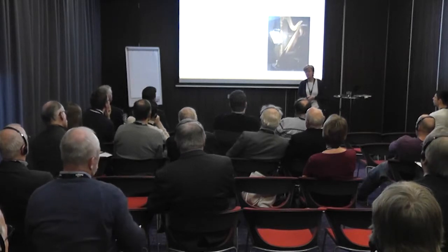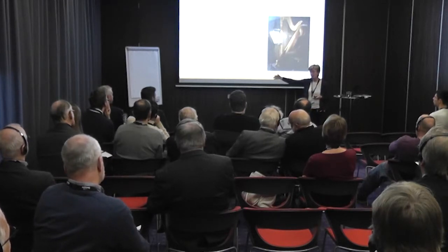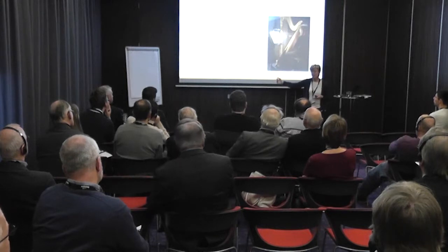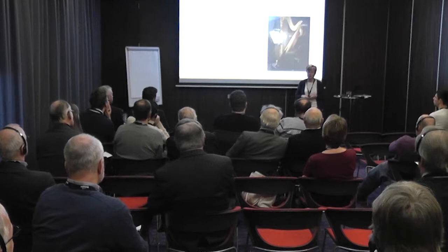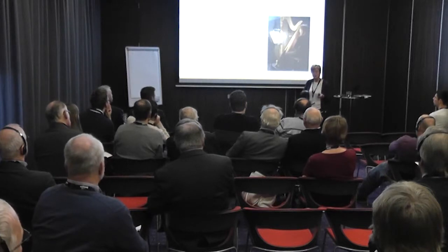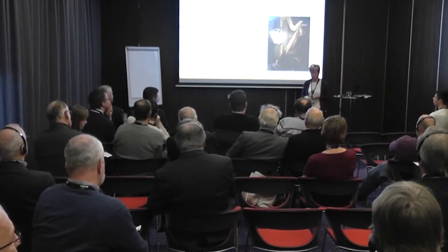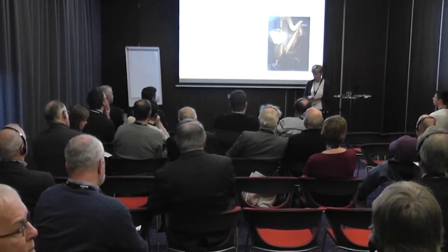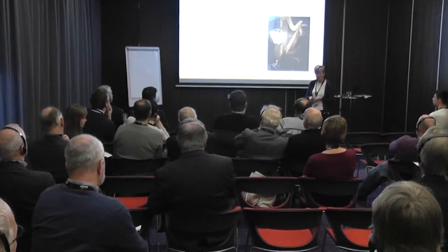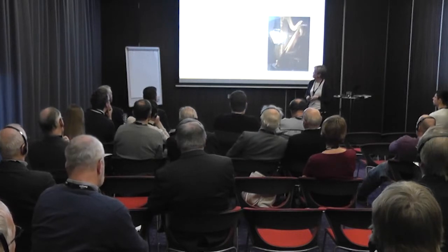So we have come to the conclusion that it's likely that these fluctuations are caused by doors open around the entrance into the orchestra pit, and also openings behind the stage that make drier air come in. So what they are now doing is putting the same humidity on all air, both in the orchestra pit and also in the main theater and the stage. This has led to, of course, higher energy use because it's a higher humidity than originally planned. So this is something one should bring further to other projects, that it's hard in one building to have different humidity zones.